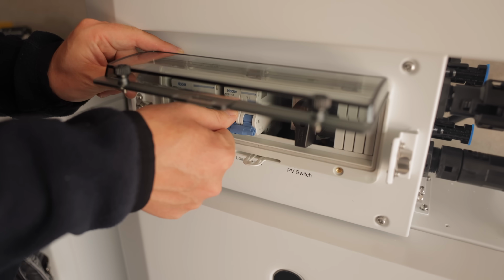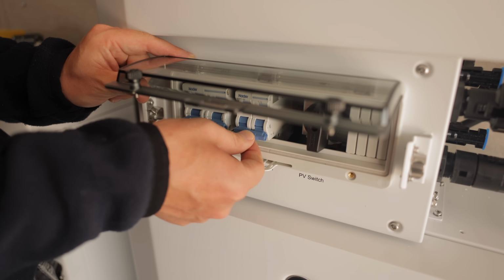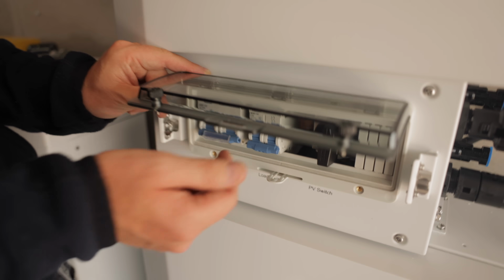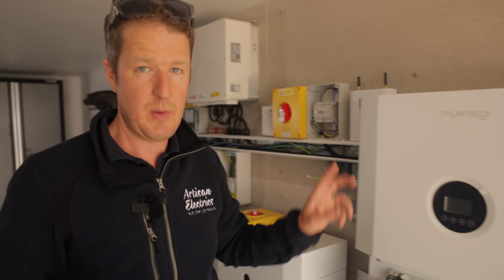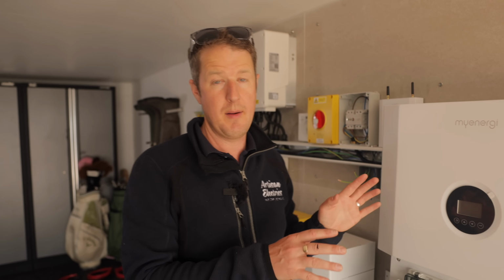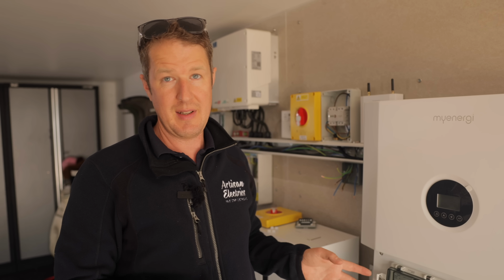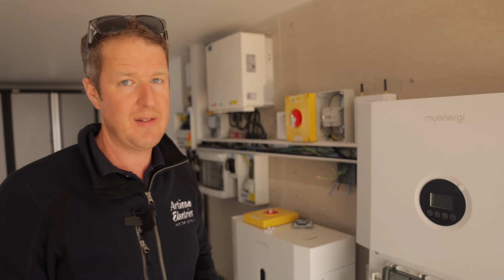However, just because it's on a 32 amp breaker doesn't mean that that's the maximum amount of power that you can run on backup. There are 2 options. With a 5 kilowatt inverter, you can run a maximum of 20 amps off of the backup circuits. With the 3.68 kilowatt inverter, you can run a maximum of 16 amps off the backup circuits. And there's one more important consideration.